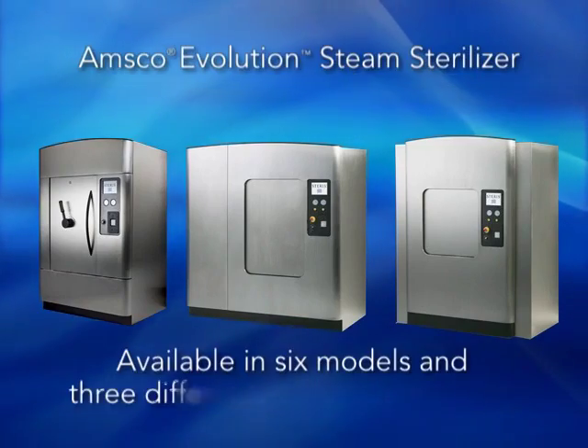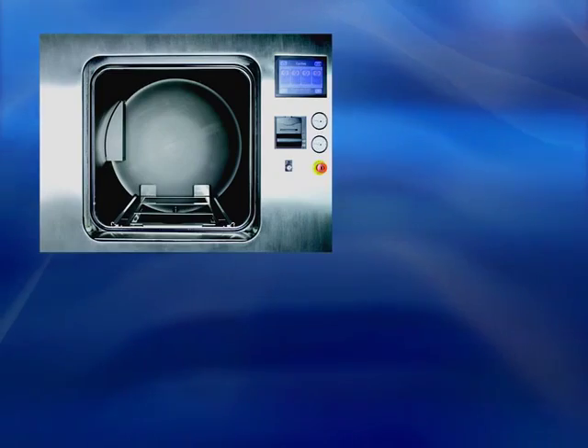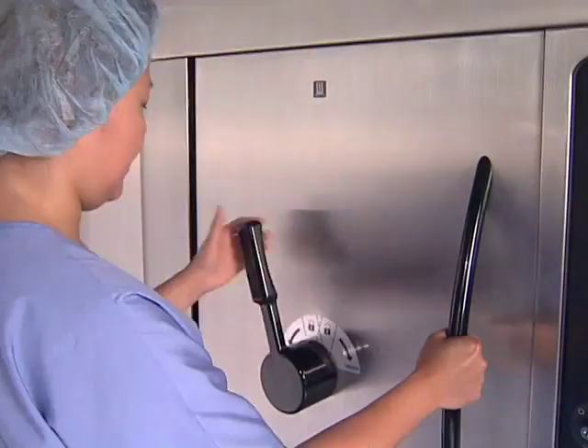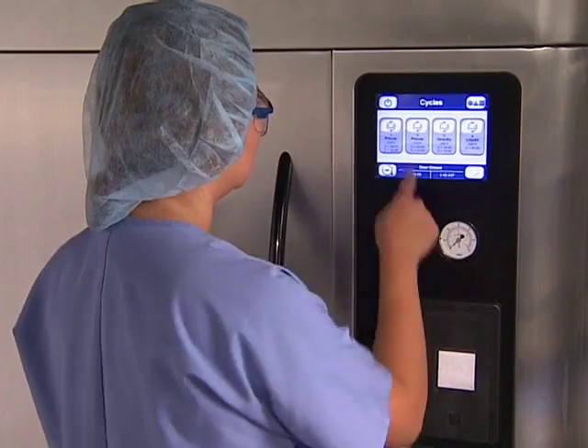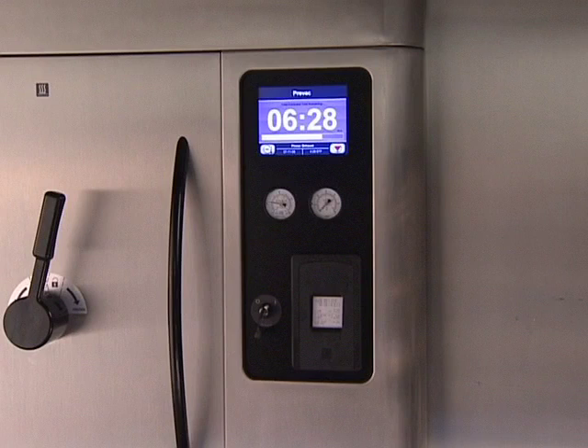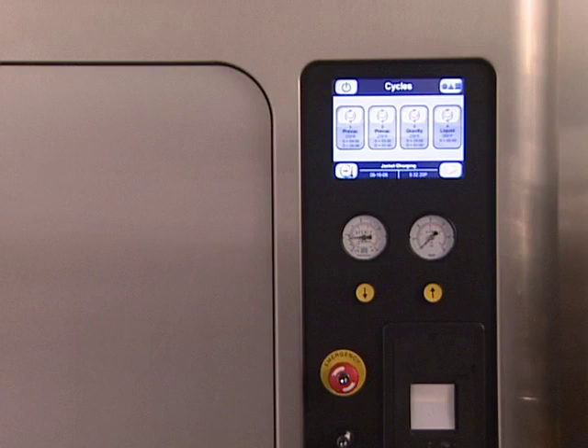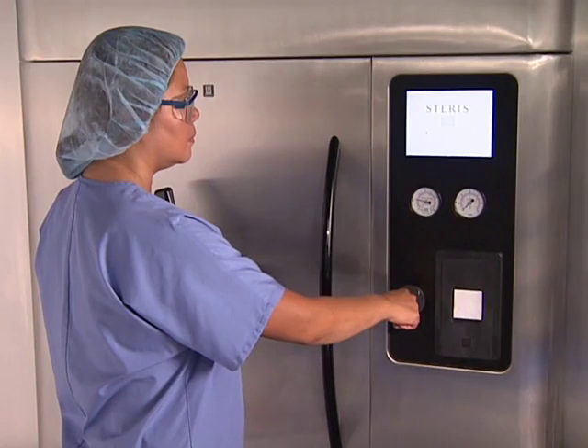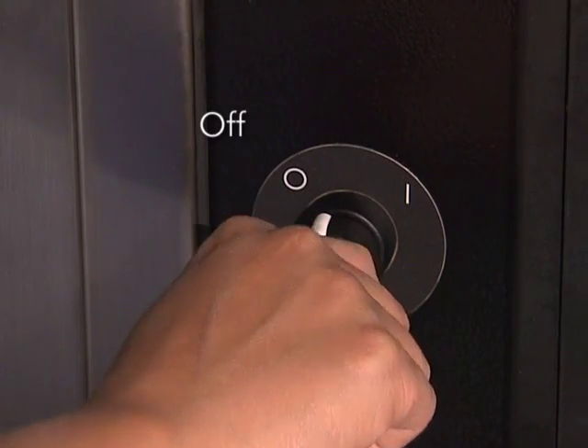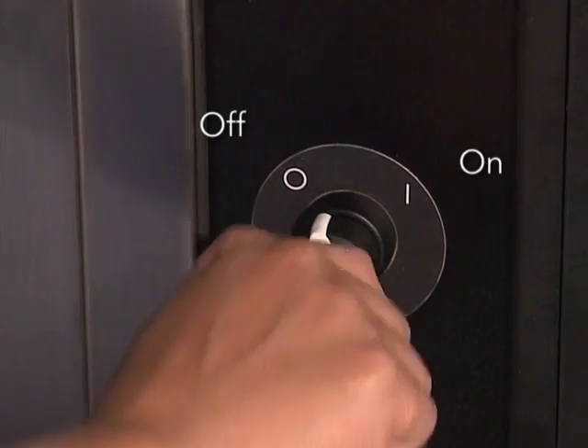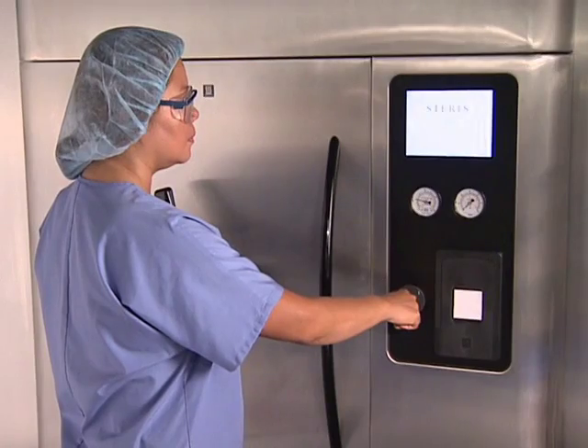The Evolution Steam Sterilizer is available in 6 models, featuring a round or elliptical chamber, manual or automatic doors, and an easy-to-use touchscreen control panel. The front side on all models houses the chamber door, control panel, pressure gauges, printer, and sterilizer power key. Models with automatic power doors also have door open and close push buttons and an emergency stop button. The control power switch shuts off power to the sterilizer control. Under normal operation, this switch is left in the on position at all times.